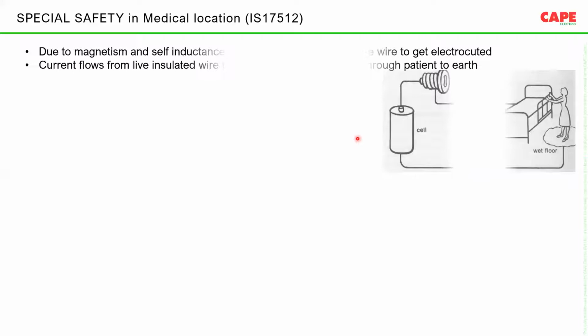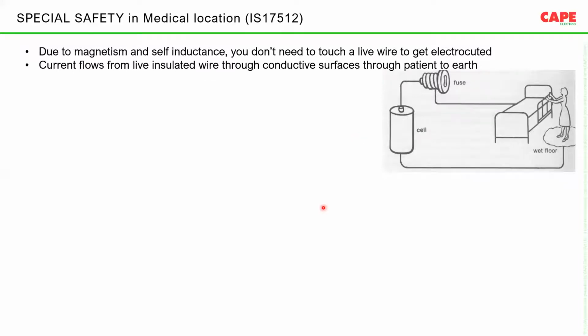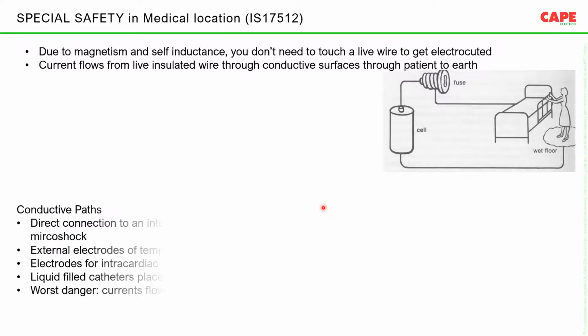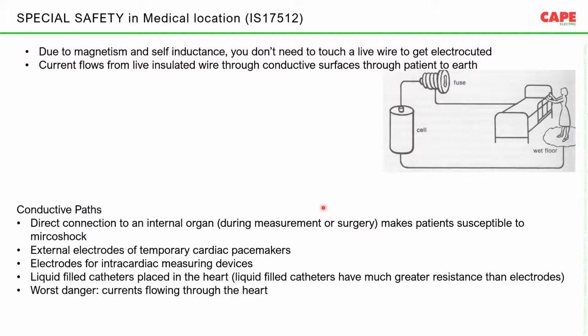What is medical location, and what is the speciality of medical location? Medical location is an area where, due to magnetism and self-inductance, even a leakage or an insulation failure is no longer necessary to create a shock situation. Even small leakages are enough to create an electrocution, and most of the time the flooring is a wet area, because most of the time it is not really dry, so the touch voltages and the chance of shock are much higher.